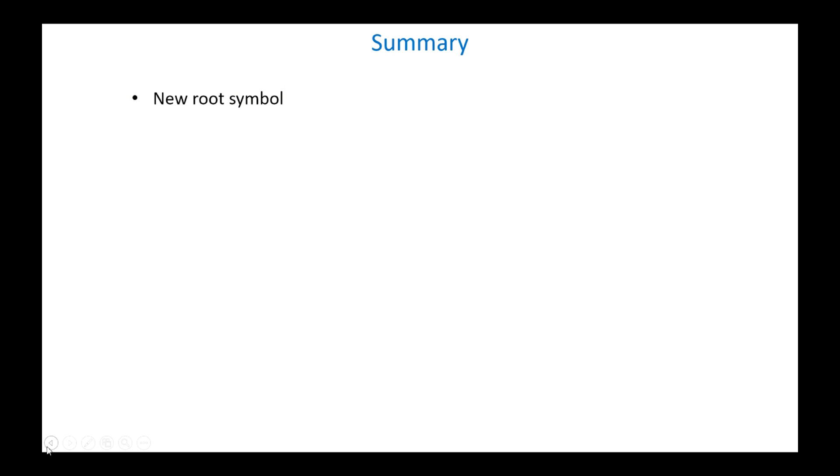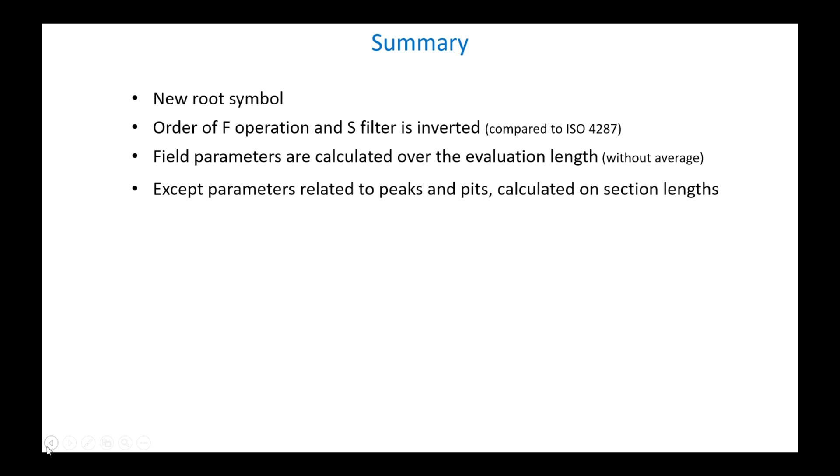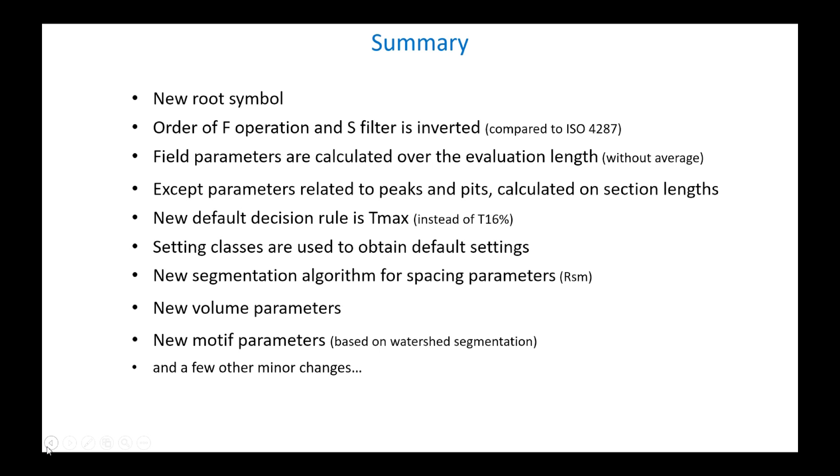To summarize, parameters defined according to the new standard are indicated with a new root symbol. The order of the F operation and the S filter is inverted compared to before, which can create differences on some profiles. Field parameters are no longer averaged over sampling lengths. However, peak parameters are still calculated as an average over section lengths. The default decision rule is now the max rule. Some parameters are associated with default settings via setting classes, and new parameters complete the range of possibilities.